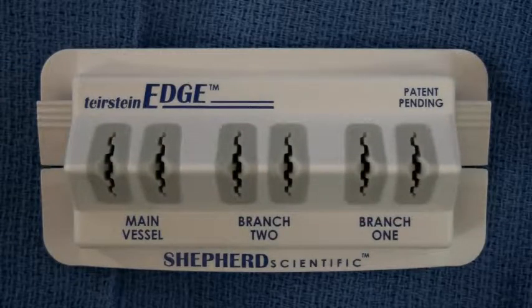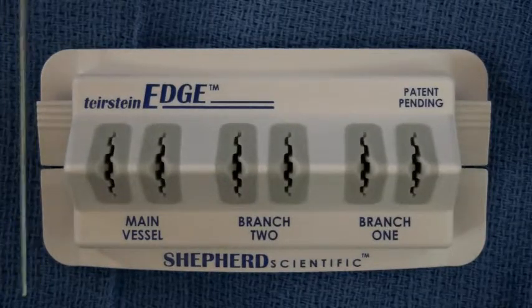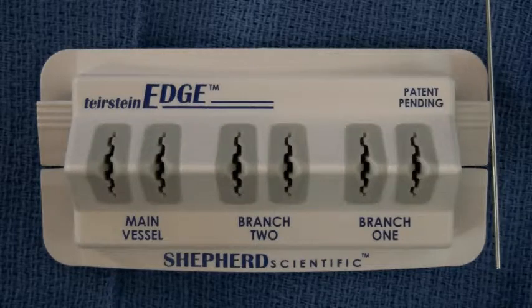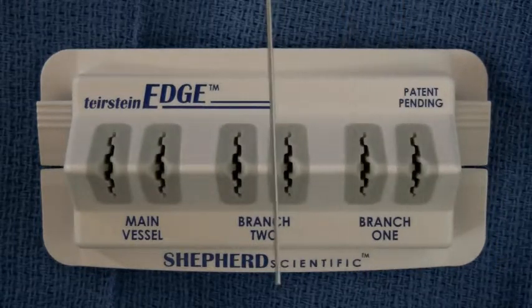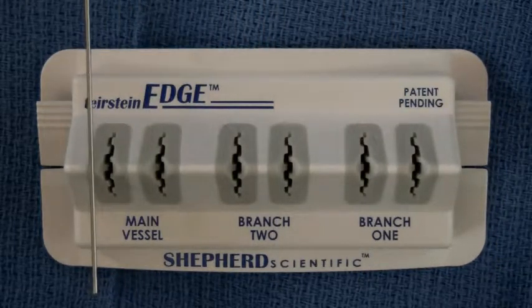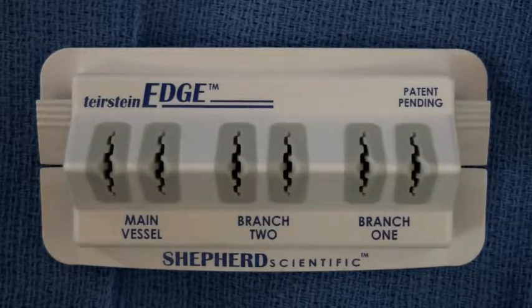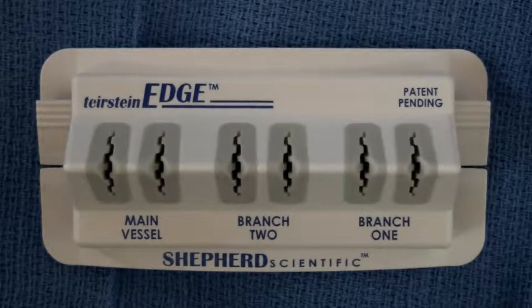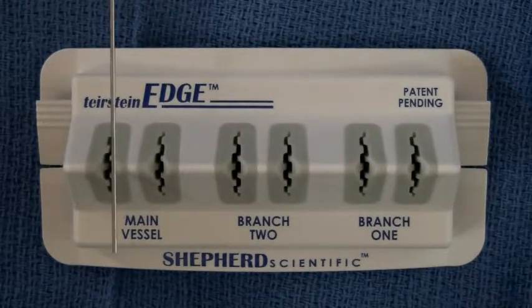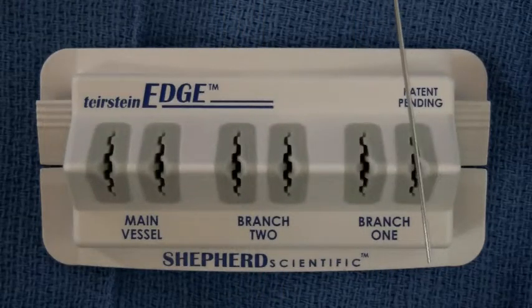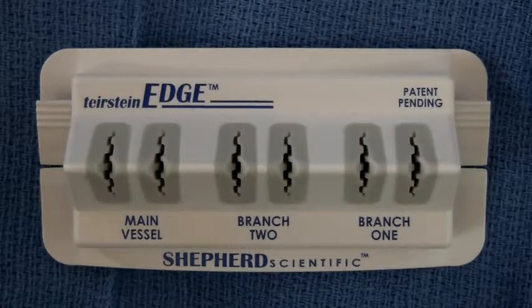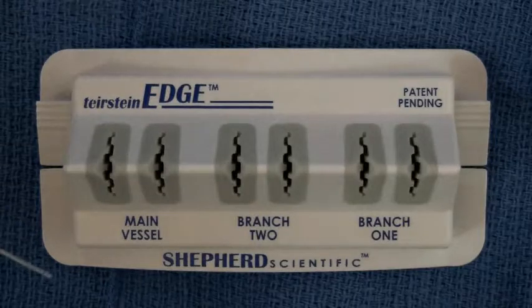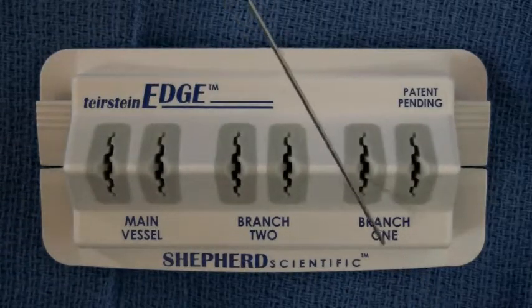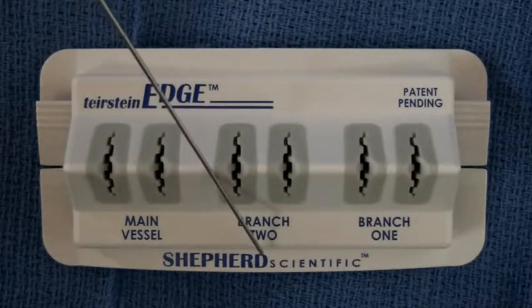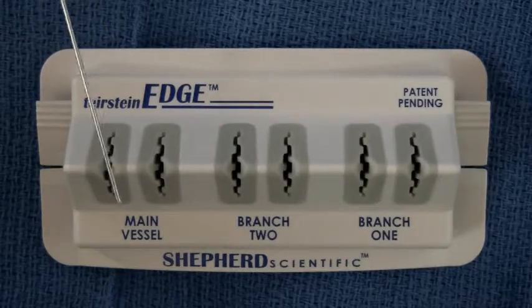The edge is intended to align and introduce interventional devices. It consists of 2 clips on either end of the device to secure the edge to a surgical towel and 6 elastomeric friction-fit slits designed to hold and organize guide wires and catheters. The slits are organized into pairs of 2, so each pair can accommodate a catheter and its corresponding guide wire. Each pair is labeled main vessel, branch 1, or branch 2.